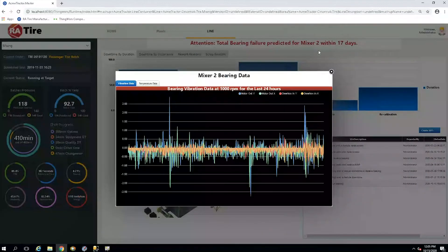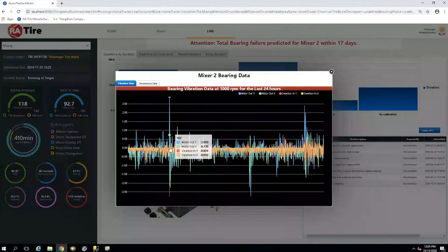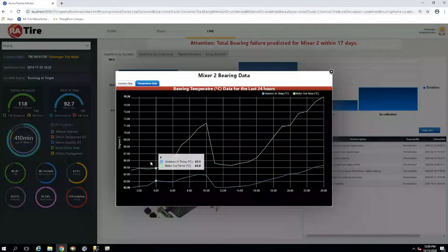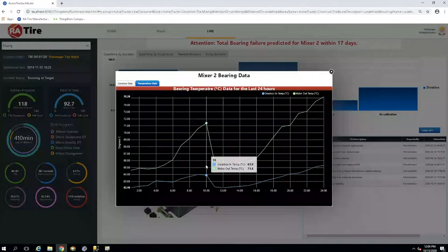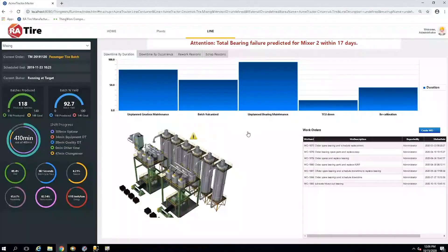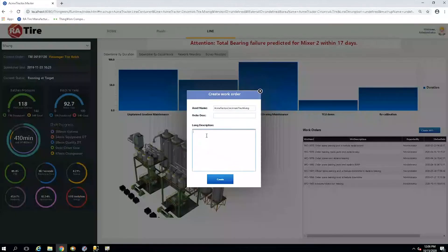Why would that be? We can click here and see the data behind this prediction. It appears that vibration is erratic for the motor outboard bearing. As we view our temperature data, it appears that this bearing was heating up and they must have lubricated it. However, throughout the day it began to heat again, indicating that this bearing is going bad. Since this prediction has merit, our plant engineer can create a work order to replace this bearing.